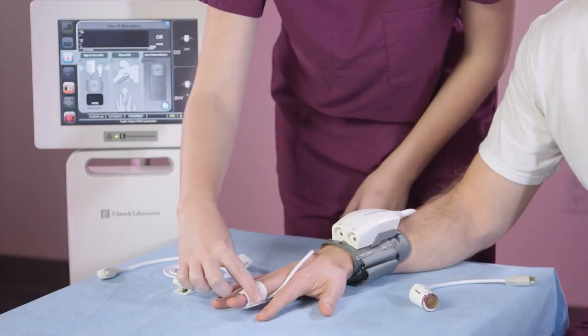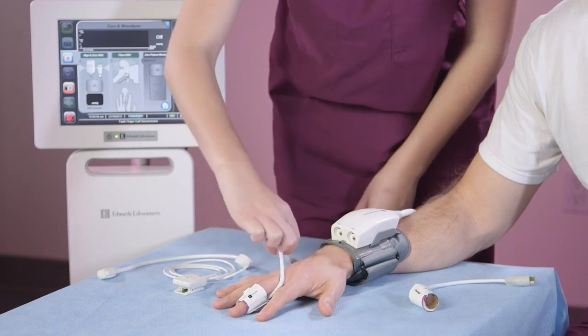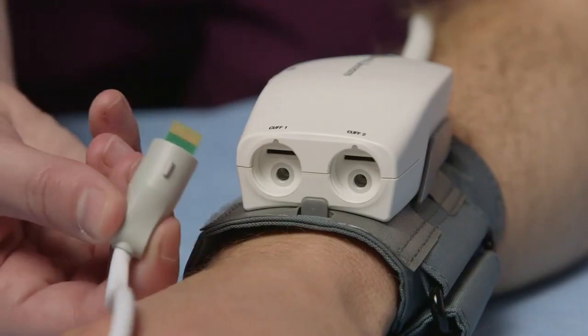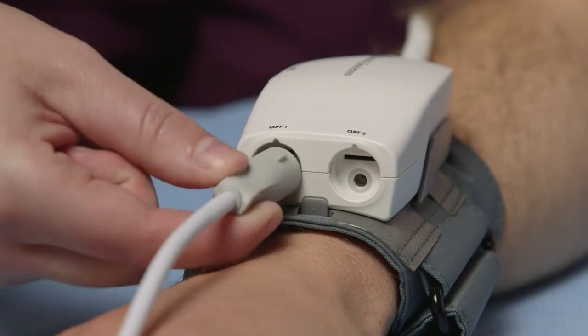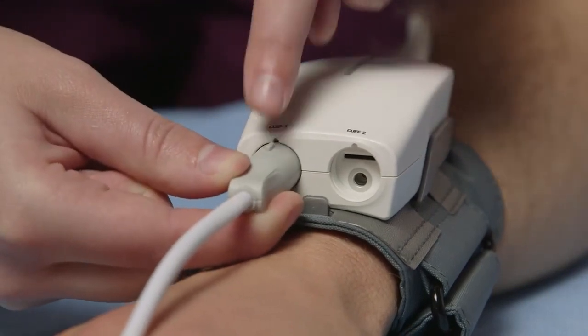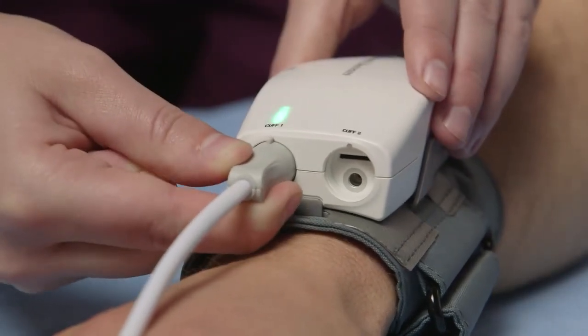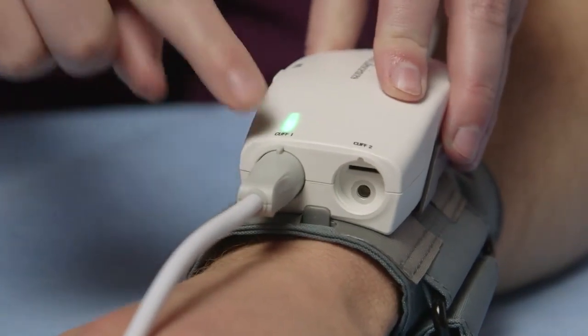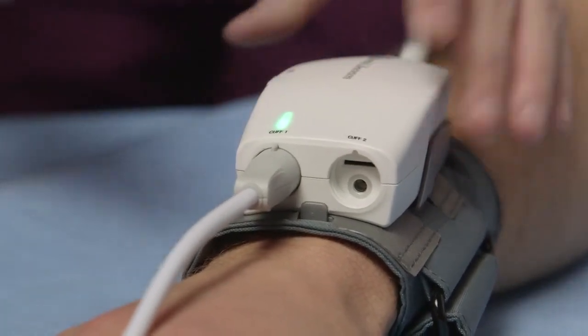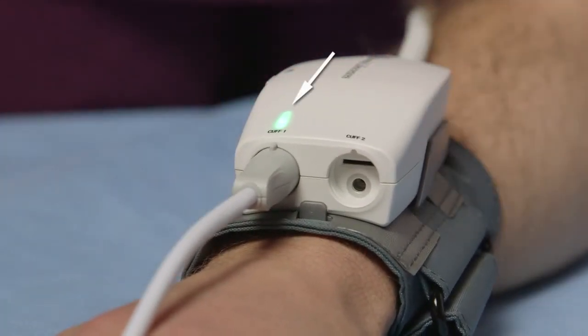Gently lead the cuff cable between two fingers toward the back of the hand and connect the finger cuff to the pressure controller in the port labeled Cuff 1. The connection enters in only one orientation. Do not force the connector into the port. When the system is properly connected, a green LED illuminates above the port. If the finger cuff is expired, the LED will flash orange and the monitor will display "Finger cuff number 1 has expired, replace cuff" at the bottom of the screen.